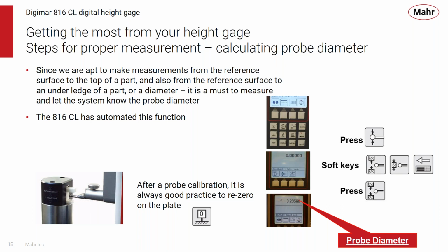The other thing that you want to do is ensure that you have the proper probe diameter as part of the measurement. Since you're apt to make measurements from the reference system to the top of the part, and also from the reference system to maybe underneath a ledge, it's important to know the measuring diameter of the contact probe. The 816 has an automated feature for doing this. On the keypad, there's one button that helps you calculate the probe diameter. You press the probe diameter key, and then you select what type of reference calibration system you have, whether it's an inside ledge one or an outside ledge one.